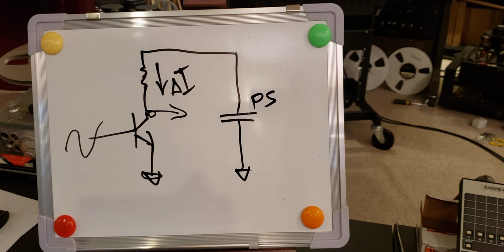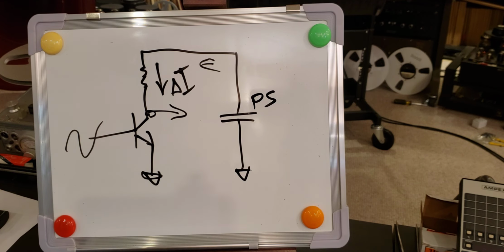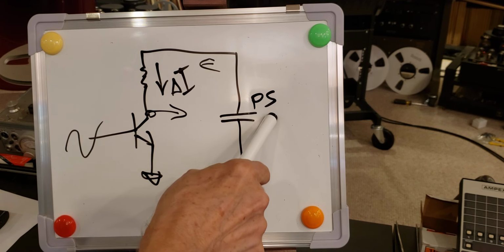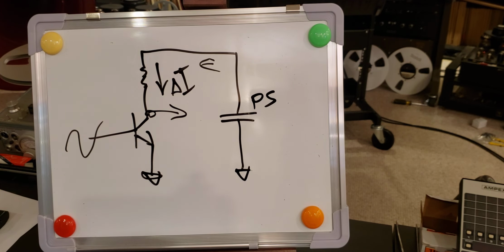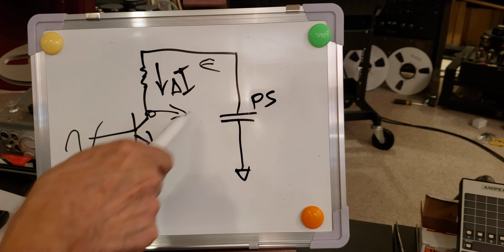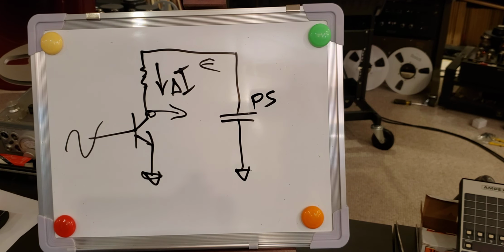The variations of signal will produce variations of current flowing through the loop, which means your power supply now has to accommodate all those current fluctuations. It might sound like a simple task, but it's a monumental one. The quality of the power supply is absolutely critical here, and a lousy power supply will prevent the fluctuated currents from freely flowing through the loop. So the demand on power supply quality is very, very high in this case, and some of those power supplies can get quite expensive.